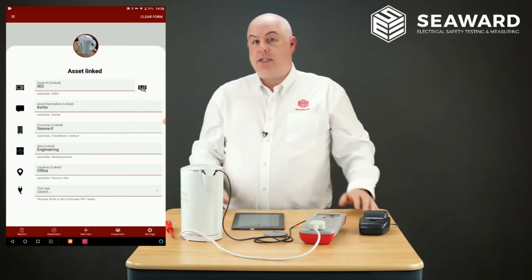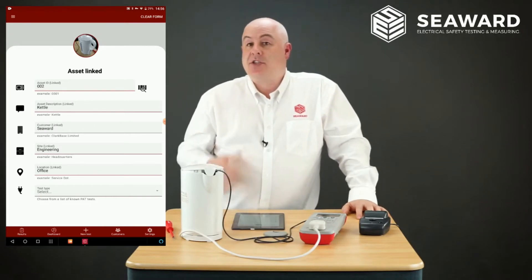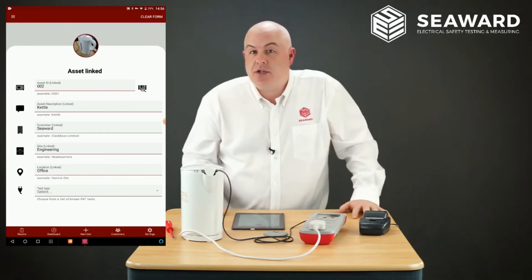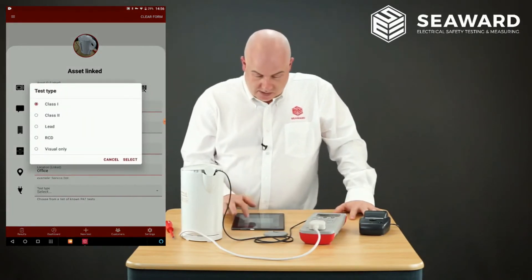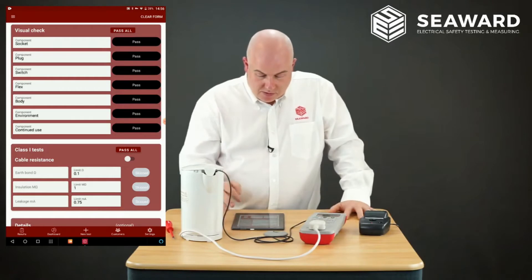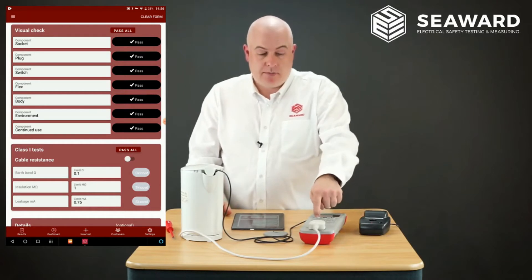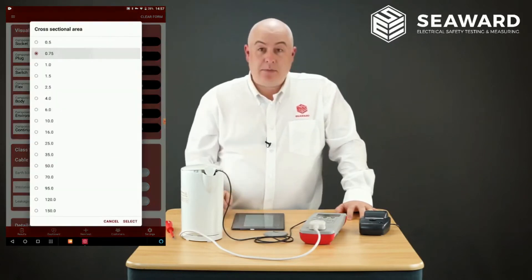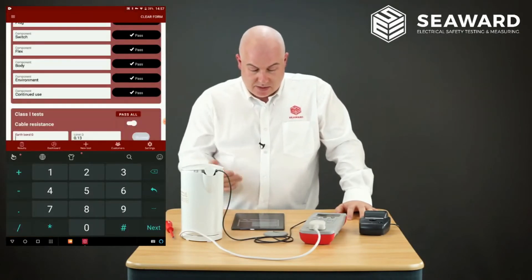You'll notice it fills in all the details for you except for the test type. The reason it doesn't pre-fill Class 1 is in case you wanted to select a separate RCD test or a visual inspection only. We're going to record a full test, so I go in and select Class 1. The usual screen comes up, I pass all the visual, and then go into the limit calculator as before — 0.75 cable, one metre lead — and it sets the limit as 0.13.